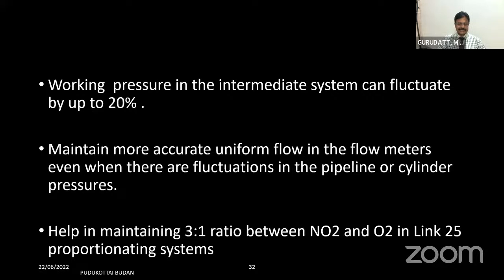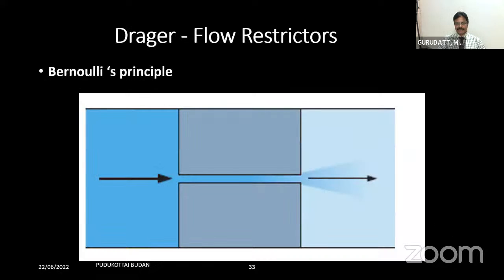Whereas in Draeger machines, there are no second stage pressure regulators, but still the pressure is reduced before the flow of gases into the flow meter assembly. That is by the flow restrictors. Though this flow restrictor is a misnomer, actually the nomenclature should have been pressure restrictor. Here they use Bernoulli's principle. Already I just discussed Bernoulli's principle.